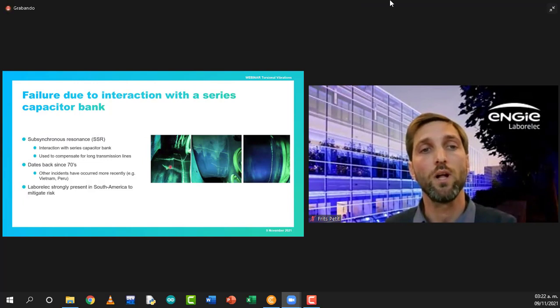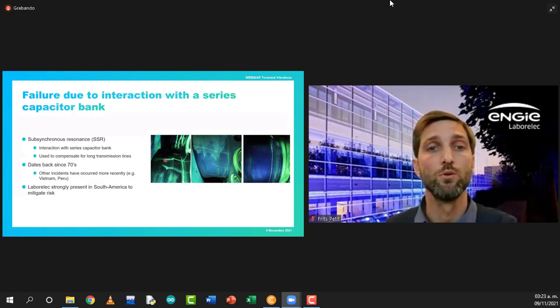Another example is a well-known phenomenon called subsynchronous resonance. So it's typically interaction with a series capacitor bank, which is used to compensate the inductance when you have a very long transmission line. So for instance, we've been involved in a study in South America. First, there was a large incident, as you can see from the pictures on the right, in a power plant with several cracks after only 200 hours of operation of the power plant. And so after this incident, the TSO was aware of the risk and actually imposed the other power plants in the same country and in the neighboring countries to perform a risk assessment study and to install protection systems to avoid things from happening as we see here in the pictures.